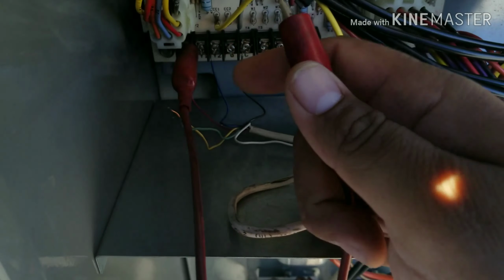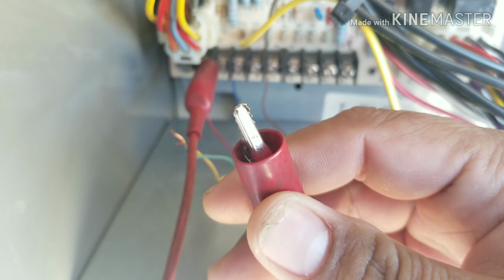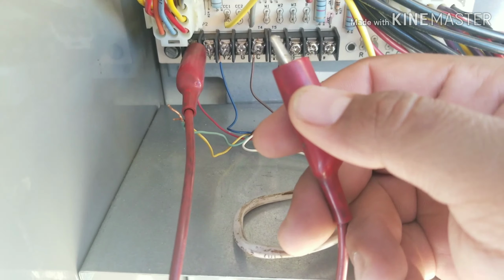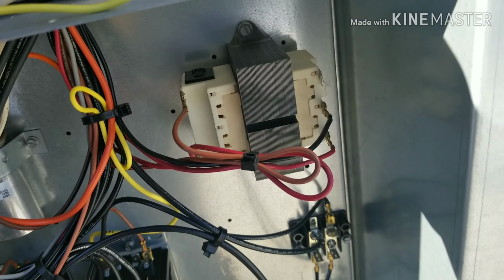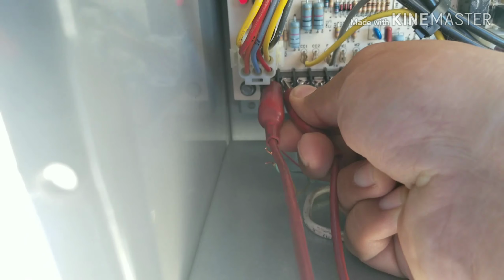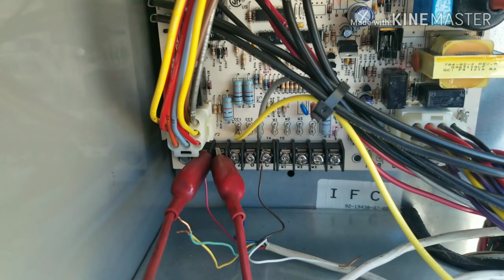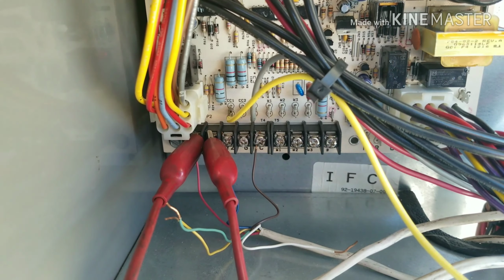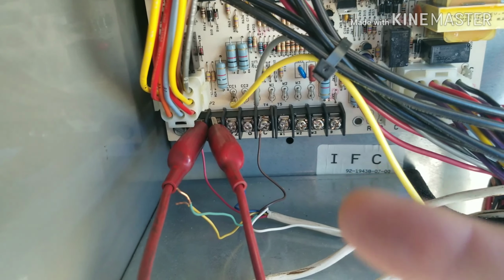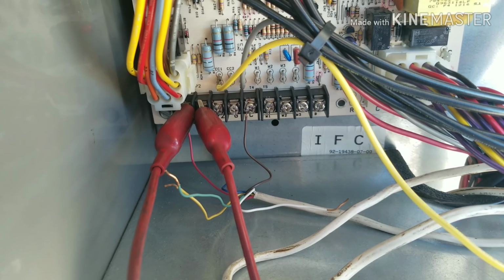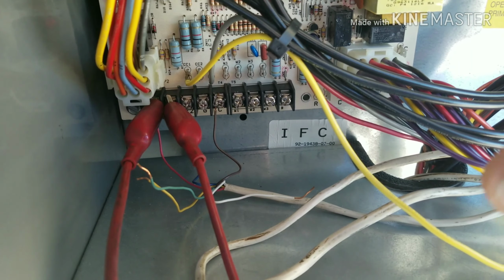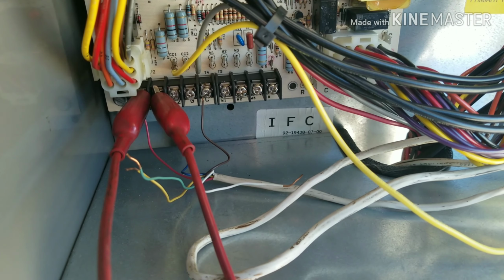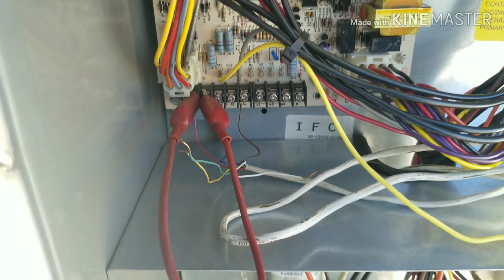So now we're gonna test the cooling. One thing to remember, guys, is that this is hot. So this has 24 volts, because you will mess up the transformer. It has a small breaker on top. So here we go. I'll make sure it's nice and snug too, because if you just clip it and you move away, sometimes these things, because it's so tense, it'll pop back out, and it could hit the metal, and there goes the transformer again too. So be careful when you do that.